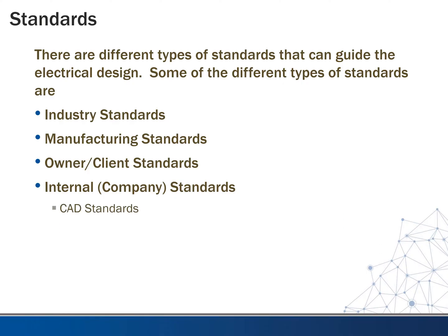In addition to that, we can have internal or company standards — something we impose on ourselves. Almost always you'll have at least some type of CAD standard, so your drawings are uniform across disciplines regarding text size, font style, and those types of things. More importantly, we can have design standards within our discipline. This can be things like only using copper bus, not aluminum bus, or preferences for certain manufacturers. At one company I worked at, they absolutely forbid us to design anything to Simplex fire alarm standards — they had some bad experience with them and wrote that into their own internal standards.